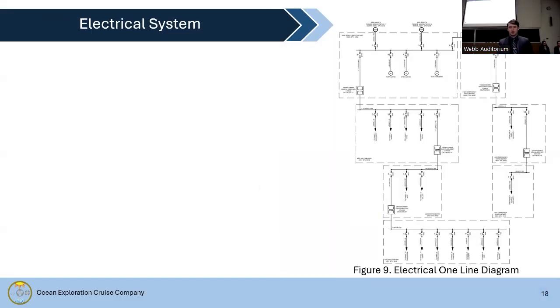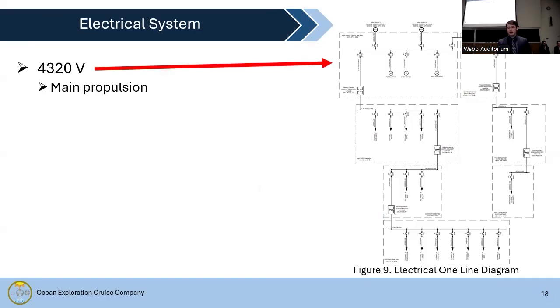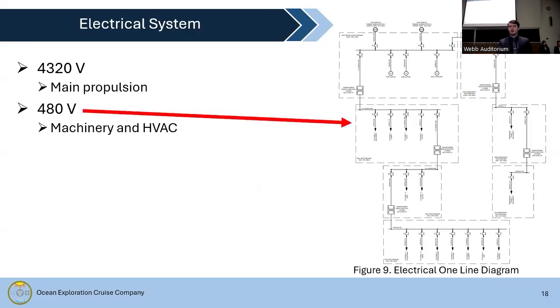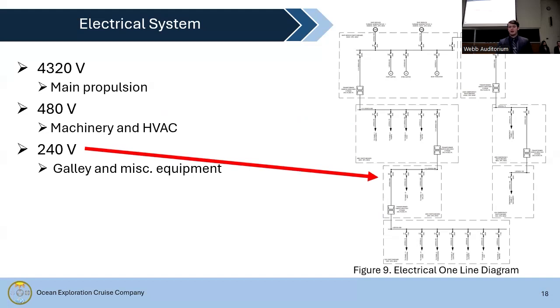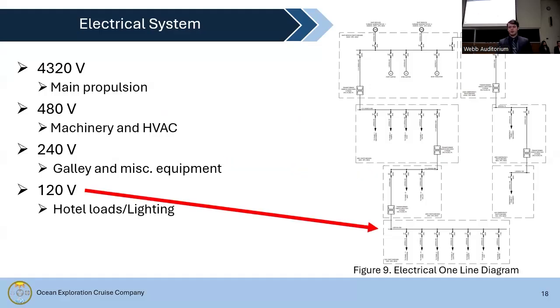Figure 9 is the ship's one-line diagram. The power generation and main propulsion are on the 4,320 volt system, and the propulsion uses 3,216 kilowatts. The auxiliary machinery and HVAC units use 480 volts and consume 1,542 kilowatts. The galley appliances and Zodiac launching equipment run off of the 240 volt system and take 325 kilowatts. The final piece is the 120 volt system, which supplies power to all smaller hotel loads, lighting systems, and other spaces. This consumes 91 kilowatts. The whole system is wired in a three-phase delta configuration.